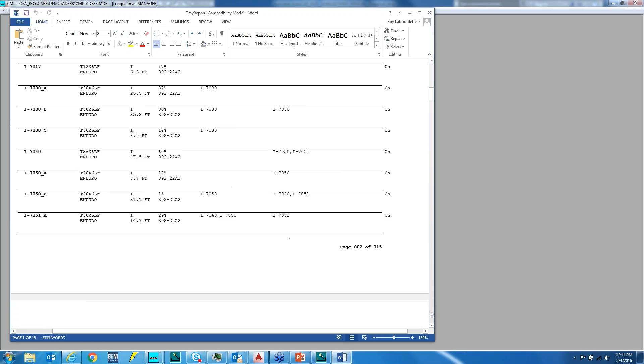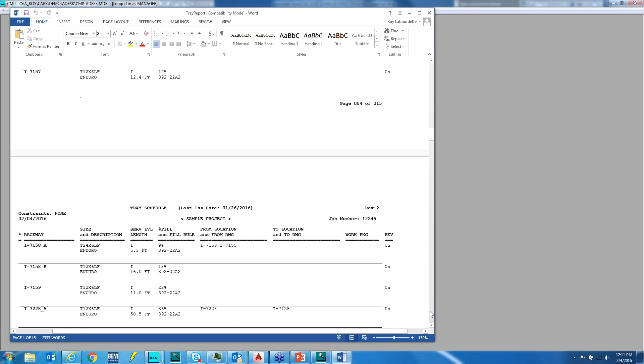But it'll give me a list of every raceway that I have on the job, and it'll tell me the fill percentage and the section of the National Electrical Code that it used to calculate that fill percentage. Now, as I flip through here, you'll notice that none of these trays are filled to more than 80% because I set my spare capacity in the program at 20%. So it will not fill more than 80%.